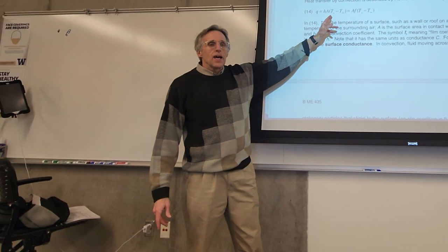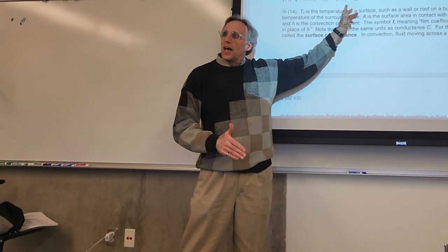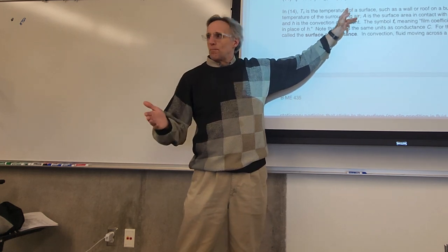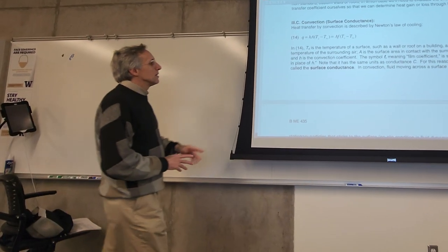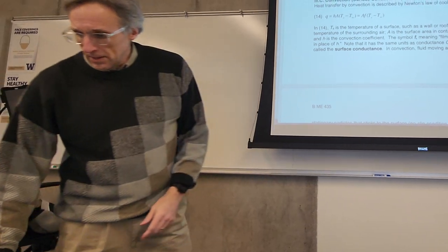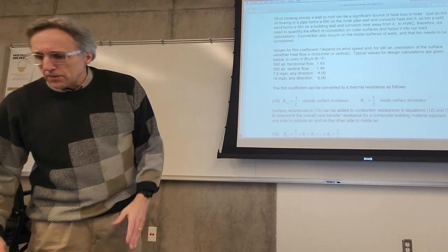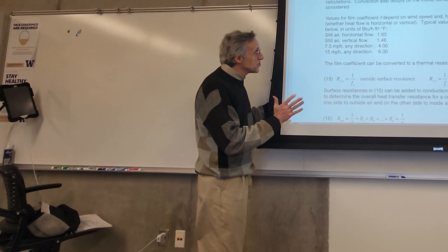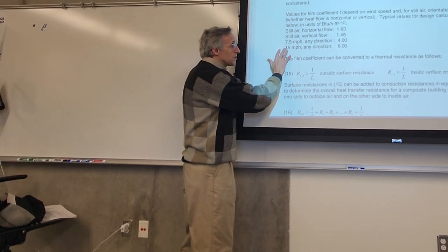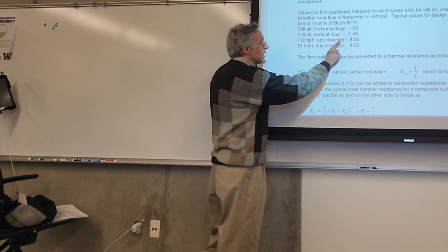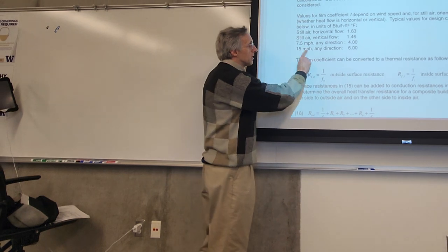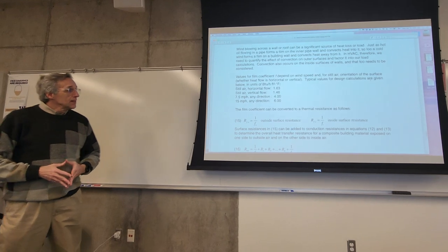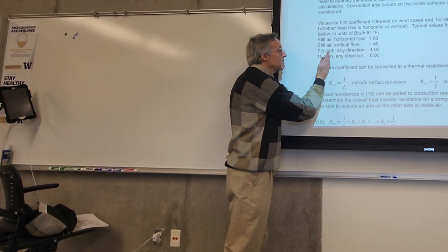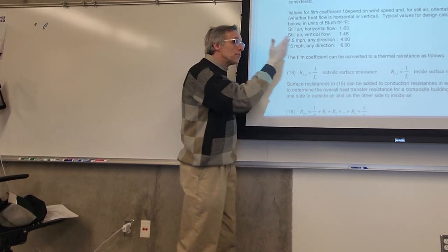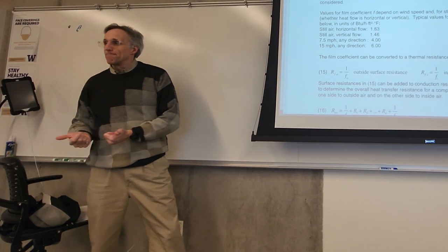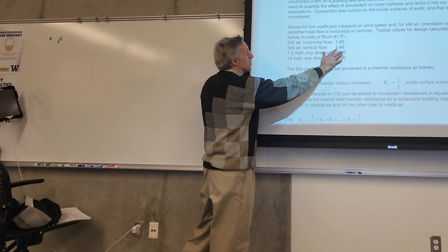I'm sorry, it's not the inverse. F is H. And the reason why some sources use F is, H is what? What's another way for enthalpy? And in order to avoid confusing enthalpy and the heat transfer coefficient, we use the F. The H or F is fairly simple to take into account in our design. We're designing for summer. We use 7.5 miles per hour wind, where H is 4, where F is 4, and in the wintertime we use 15 miles per hour, so we get a little bit more heat transfer on the outside. H is 6. And then inside, where you don't have much air movement, you still have some, and even with no air movement, you have heat transfer by natural convection, right? But a smaller heat transfer coefficient inside.